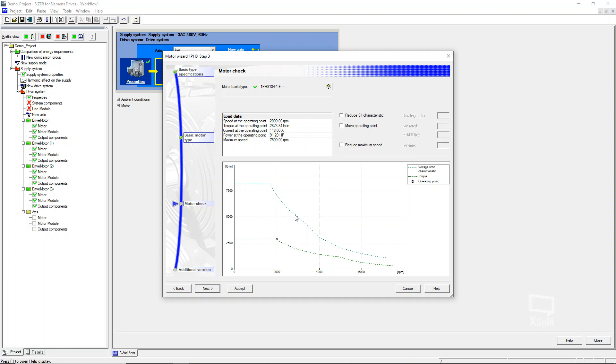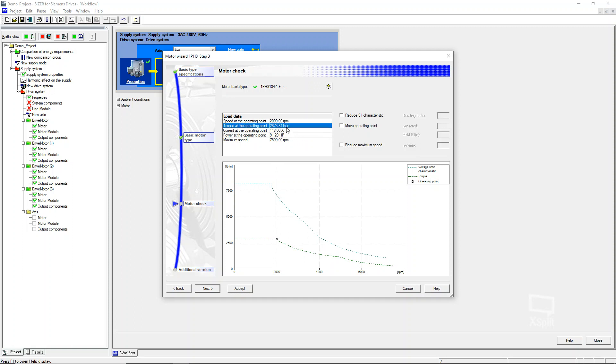Click next. And here is the magic screen for motor data. This is actually going through and saying how are you actually going to use this motor, because this is what Sizer is going to use in order to size the drives. Most of the time you're going to be just looking at the nameplate rating on this. For this motor, that nameplate is 2000 RPM and then this 2873 inch pounds of torque. Now this inch pound rating here is based on that US NEMA rating that we set up earlier.